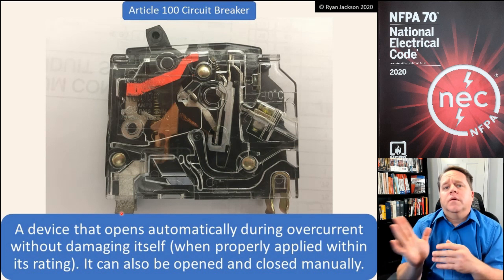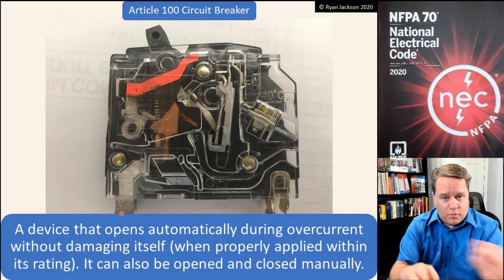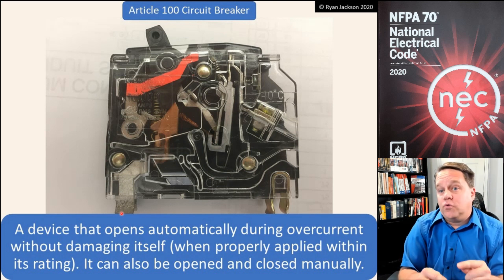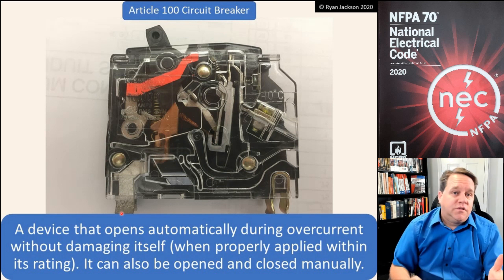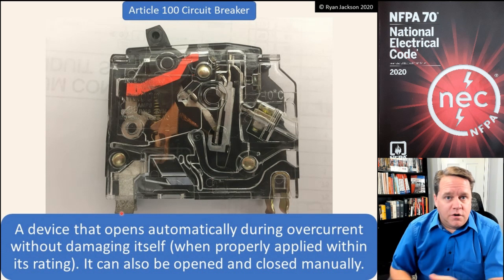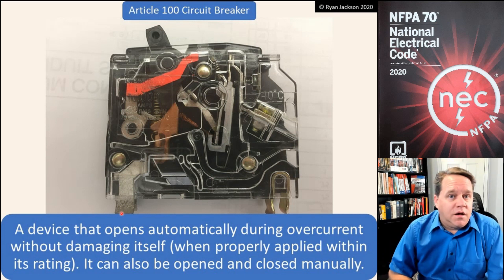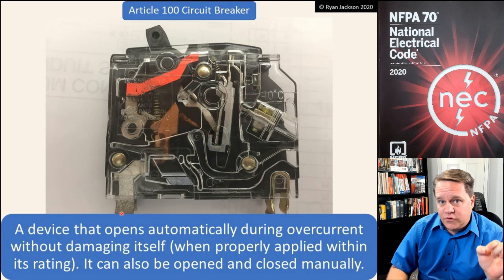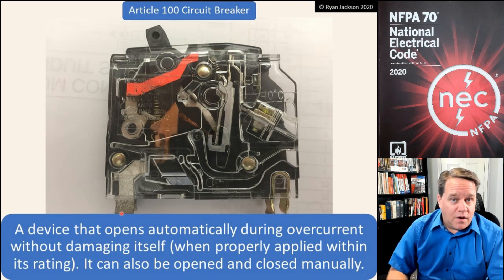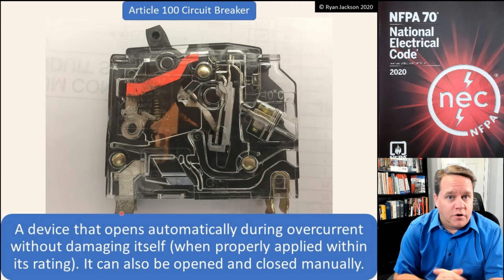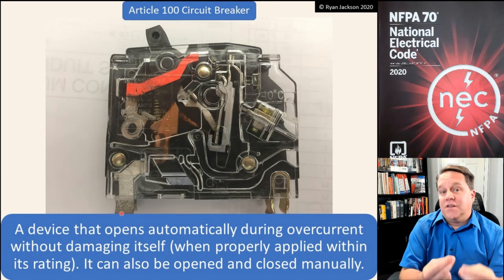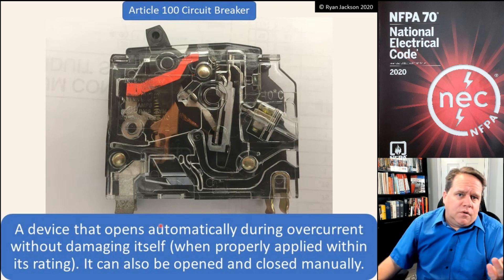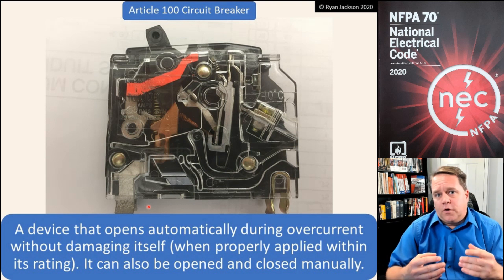Once it cools down, the bimetal goes back to its original shape and we can reclose it. If it hasn't cooled down enough — for example, if you plug in 10 hair dryers, trip the breaker, run downstairs and reset it, then plug them right back in — it's going to trip pretty quickly because the bimetal has already heated up. If we let it cool down, we'll be able to use it for a longer duration before the bimetal changes shape and opens the circuit again.